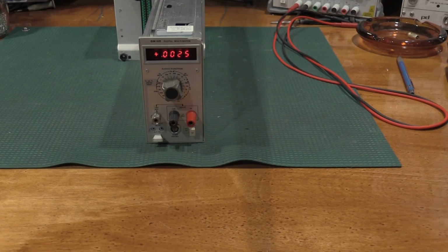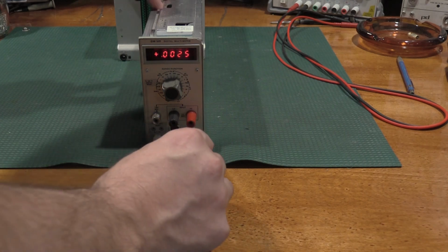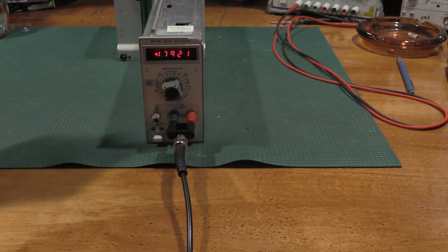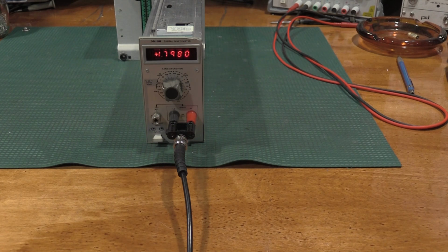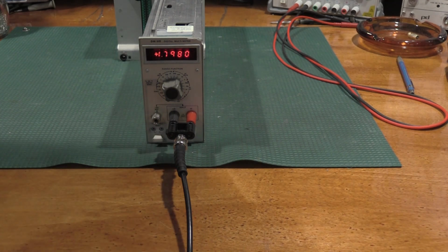Okay, and using the same cable that I was measuring this on the DM501, we have 1.8 with 4 zeros on the back of it. That's plenty good for checking this meter. And we are off, actually. So that's going to need an adjustment. And it wants it to an accuracy of 1 count. So that's 1.8000. So that is not going to be sufficient.